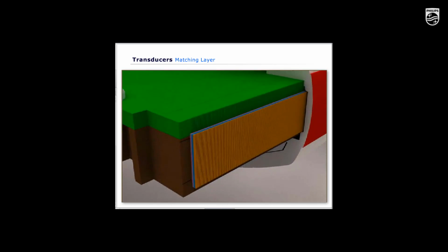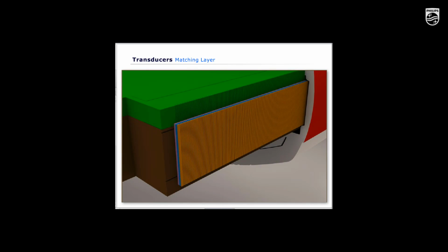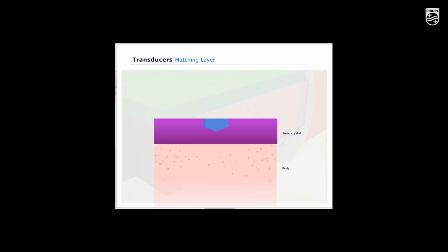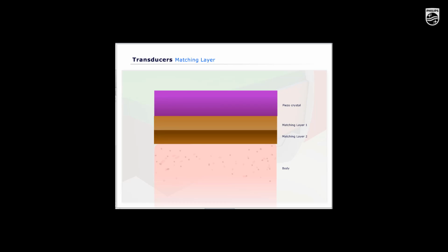Because the transducer element is a solid, it has an impedance that is about 20 times that of tissues. Without compensation, 80% of the emitted intensity would be reflected at the skin boundary. To solve this problem, a matching layer commonly is placed on the transducer face. Its function is to improve sound transmission to the body, reduce the reflection of ultrasound at the element surface, and allow most of the ultrasound energy to exit the front of the element.